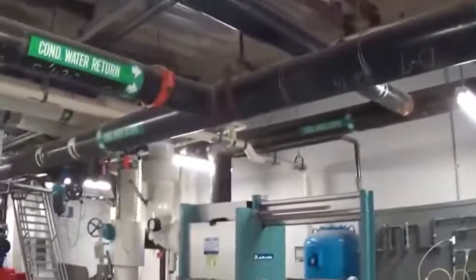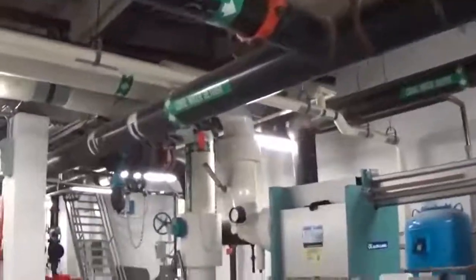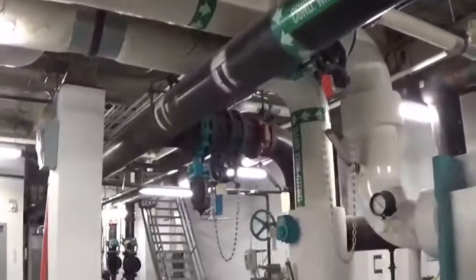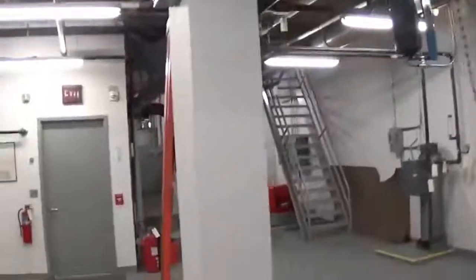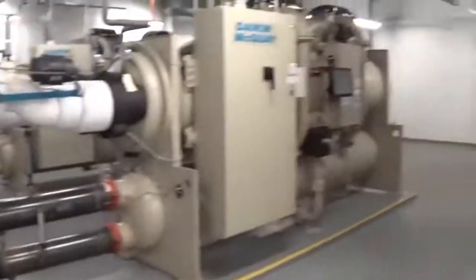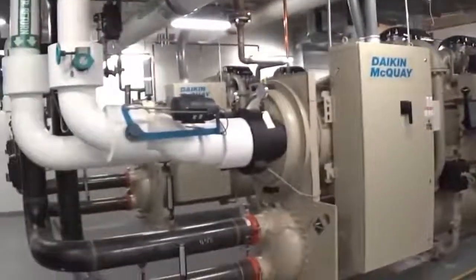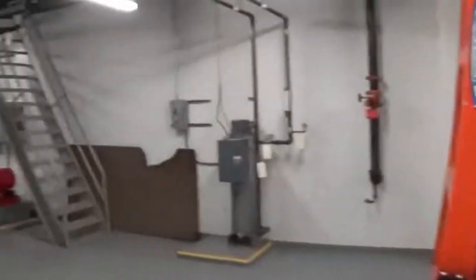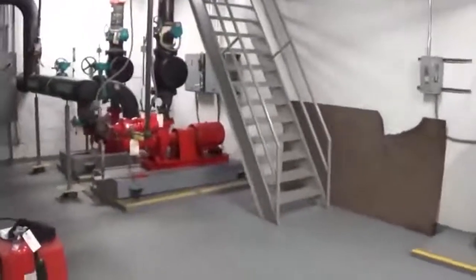And we'll take a look at the cooling tower. Now, this is a water side condensing chiller plant, and they require a lot of maintenance. As you can see, this one is pretty much kept immaculate. Guys do a great job here. But you do have to attend to your chiller plant pretty much 3 or 4 times a day.